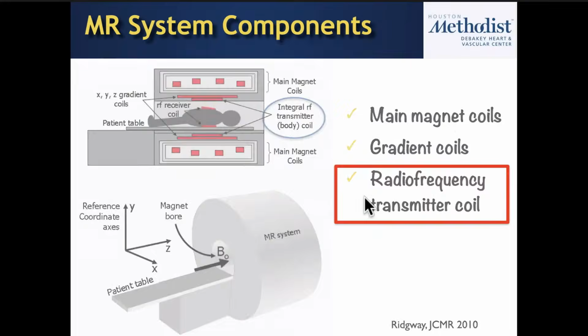And then in addition to that, there's also receiver coils, which actually receive radio waves. So the idea is you're sending in radio waves to cause excitation of protons, and then you're receiving radio waves back, which allows you to get signal to be able to then generate your image. And these radio frequency coils are typically what you see as surface coils that you place on top of a patient. There's also a second set of coils that's in the table itself. So these are called posterior coils or spine coils. And so essentially you've got coils on both sides of the patient, on the front of the patient, as well as on the back of the patient.